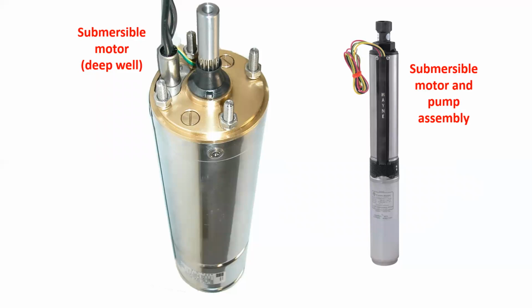We also have some very unique motors that are for specific types of applications. This one is a submersible motor, and it's meant to fit inside the diameter of a deep water well. They're also used in oil and gas. So this type of motor is actually suspended by the pipe that the pump will push the fluid up, and the wires for its connection are zip tied to the pipe. And it could be down a deep well upwards of 100 meters.